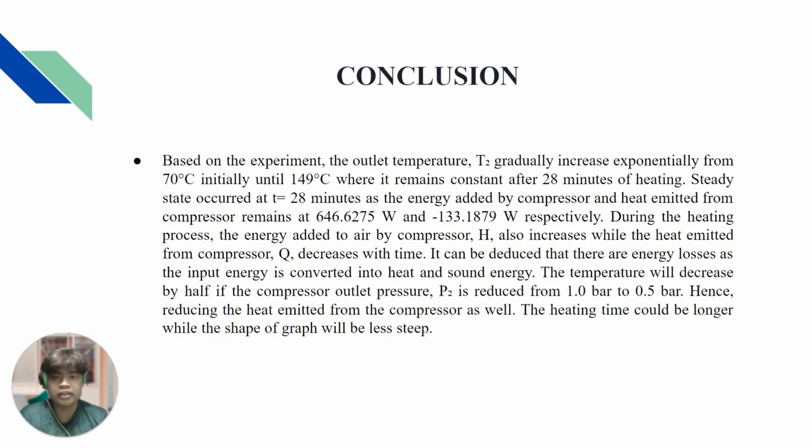Steady state occurred at t equals 28 minutes as the energy added by compressor and heat emitted from compressor remain at 646.6275 watt and negative 133.1879 watt respectively. During the heating process, the energy added to the air by compressor Hc also increases while the heat emitted from compressor Qc decreases with time.